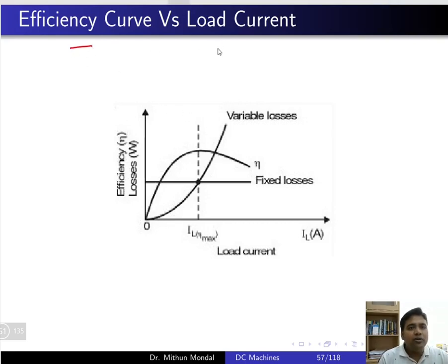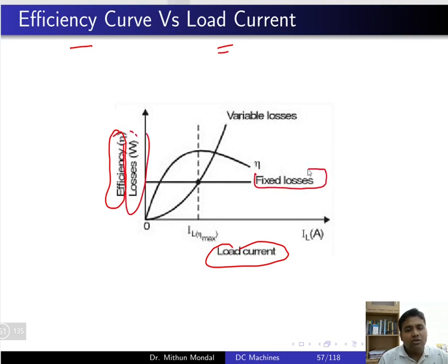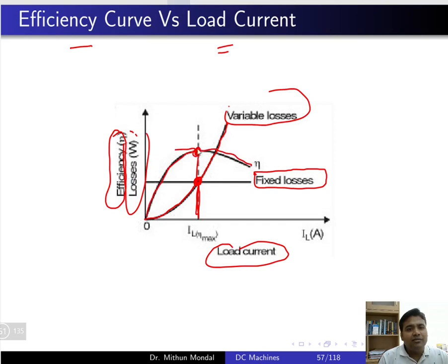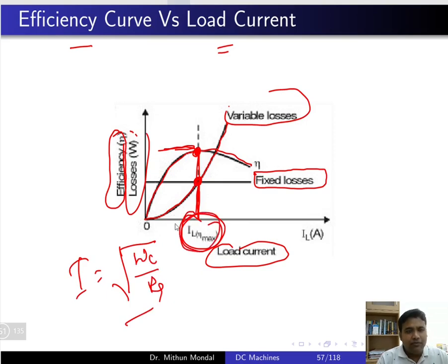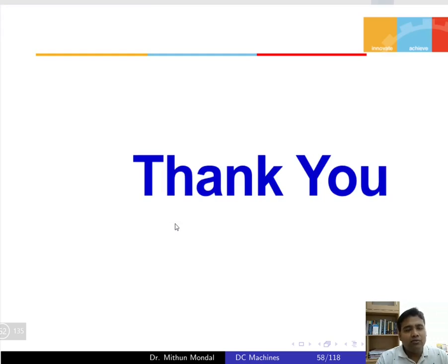If you draw the efficiency curve with load current on the x-axis and efficiency on the y-axis, the fixed loss is a horizontal line parallel to the x-axis while the variable loss increases with load current. At the intersection of fixed and variable loss curves, efficiency is maximum. The current at which maximum efficiency is achieved is I = √(constant losses / Ra).